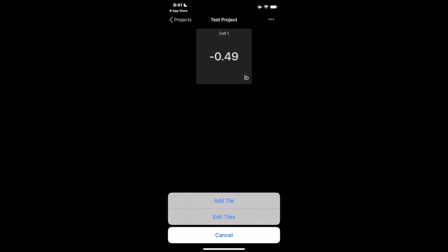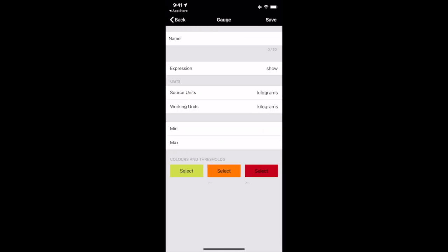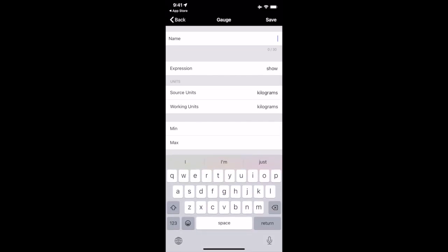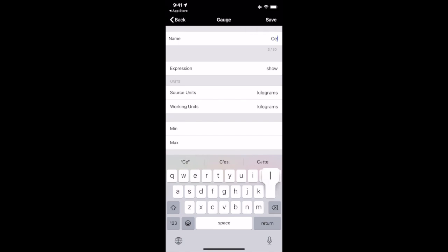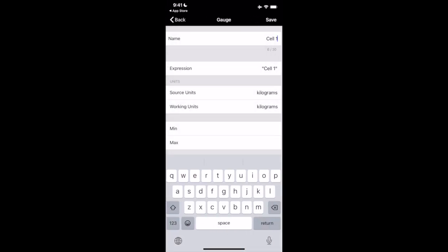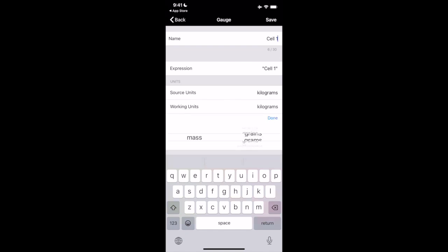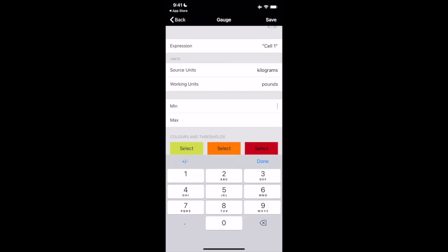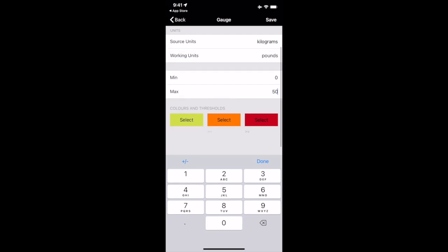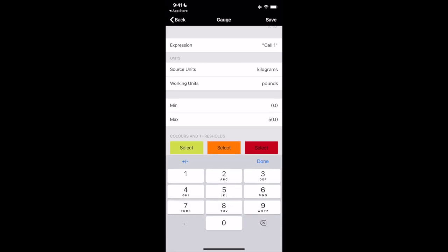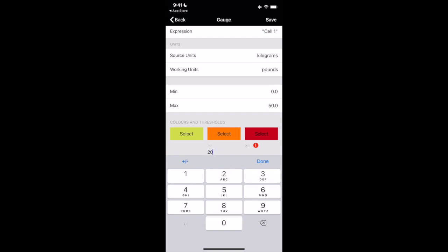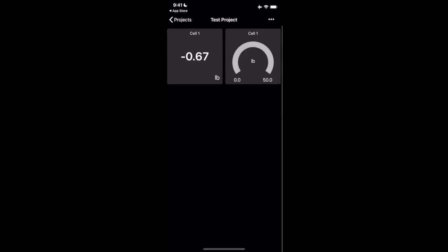If you want to do an additional tile, I'll show you one more. While we're talking about this, come in here, add tile. Let's do a gauge tile this time. So let's also call it cell one. Cell one, we're going to look at transmitter cell one. We're going to save that. Source units, kilograms, working units, we are going to come back down to pounds. And minimum on the gauge, we're going to do, let's do zero. And just because I'm pulling this by hand right now, let's call our maximum 50 pounds. Perfect. So we have a gauge from zero to 50 pounds. When I click save, I have to do a threshold in here. So let's just do 20 and 40. We'll save that. Perfect.